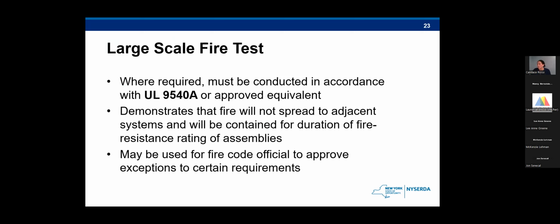Most of the design requirements for energy storage are to ensure that if there is an incident or fire, it does not spread to neighboring cells, modules, or racks. This also needs to show that if a fire does occur, it will be contained within the area for the duration of the fire resistance rating of the room assemblies. And the test report must be provided to the fire code official for review and approval. There are also a few requirements throughout the code that can be altered based on the results of large scale fire testing, and that's something I'll highlight as we go through the presentation.